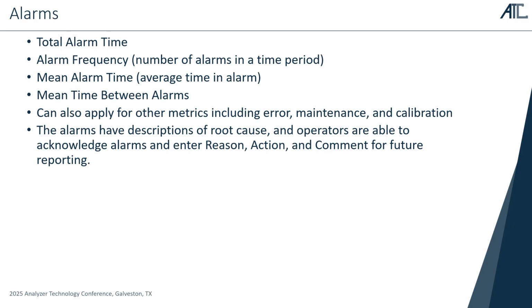And whenever an alarm is generated, the typical procedure is for the operator to acknowledge it and submit a reason, action, and a comment, which can then be used to further investigate the root cause, perform the root cause analysis, as well as show it in case of a system audit. You're able to go through the system and show the auditor how the system was performing, the various deviations, and the quality assurance for that system. And this is where the reporting, having all that data in the report, is very important, and the electronic operator logbook is important as well to track all the changes to the system.